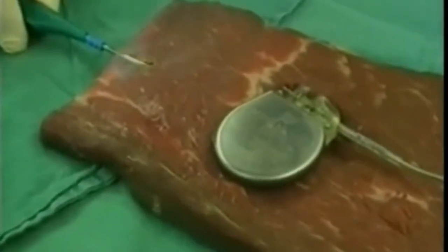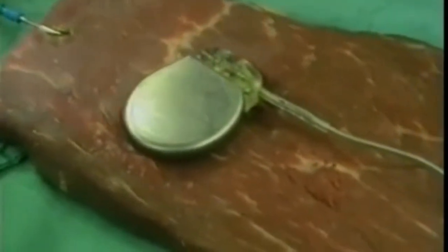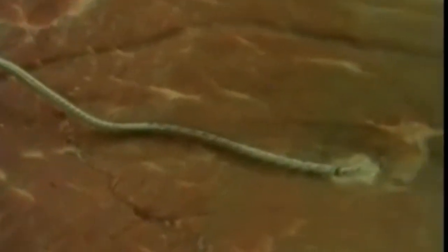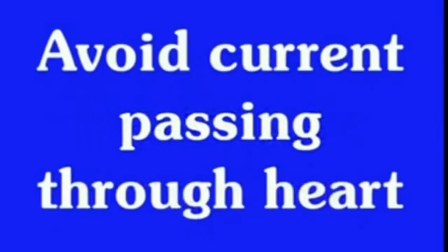Electrosurgical current can create voltages in the pacemaker lead, which can cause a heating effect at the point of contact with the endocardium, leading to failure of the pacemaker. If the patient has a pacemaker, it's wise to use bipolar electrosurgery. If this is not practical, the patient return electrode should be sited so that the current does not pass through the heart or the pacemaker lead, and power settings should be kept low.